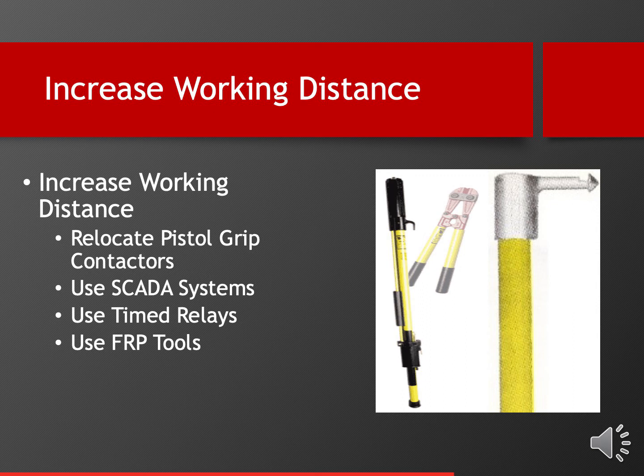Using supervisory control and data acquisition systems, often this would be fiber optic systems, to be able to reset a breaker, for example, from a control room rather than doing it while standing in front of that breaker. Again, a great option. Some companies have used timed relays, meaning after you close the switch in, and when you actually actuate the handle to close it, it actually just starts a timer, which will give you, say, 15 seconds to get out of the way, and then it'll close the breaker in a retarded fashion. Again, a great option if that makes sense for your facility.